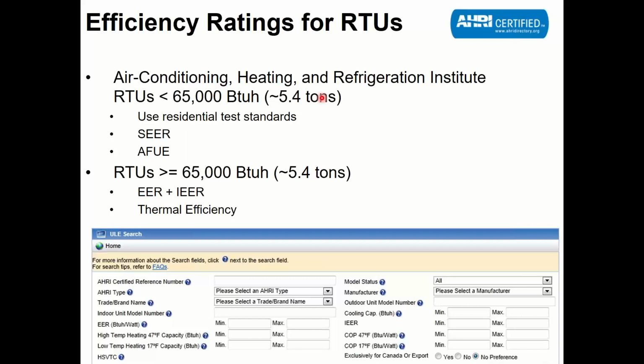It's ARI and GAMA merged together like 15 years ago. It's basically a collection of all of the manufacturers as well as some other stakeholders that get together and write the standards on how stuff should be tested. And the reason for that is to make it so I can compare manufacturer A to manufacturer B in a relatively fair fashion. In any case, for small stuff, it gets to use the residential standard, which means the main rating for cooling would be SEER, just like it is for your house.